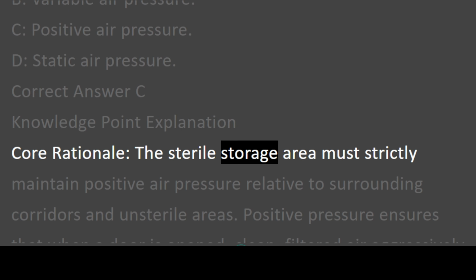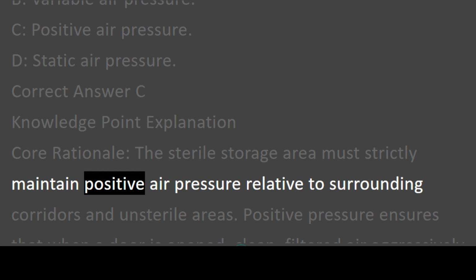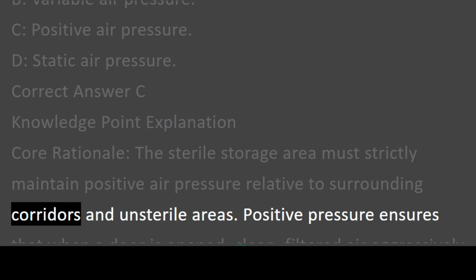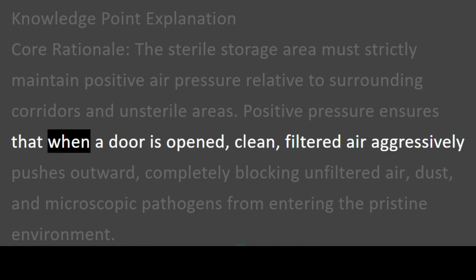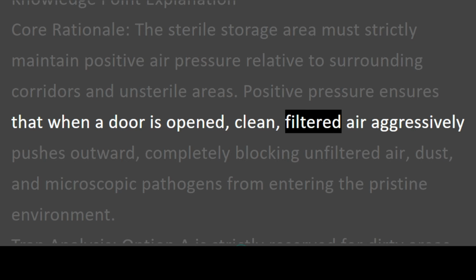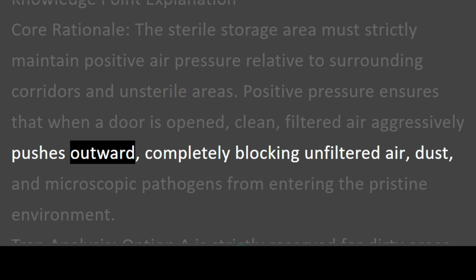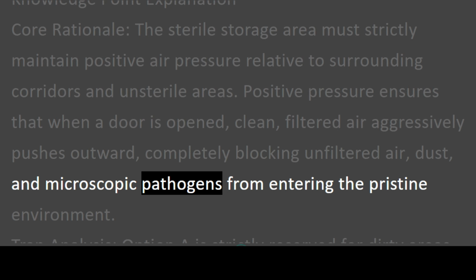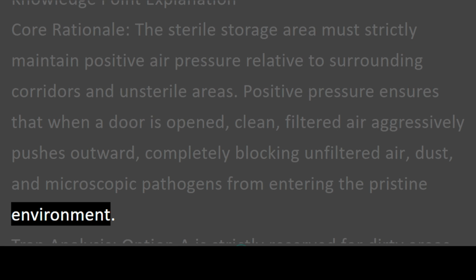The sterile storage area must strictly maintain positive air pressure relative to surrounding corridors and unsterile areas. Positive pressure ensures that when a door is opened, clean, filtered air aggressively pushes outward, completely blocking unfiltered air, dust, and microscopic pathogens from entering the pristine environment.